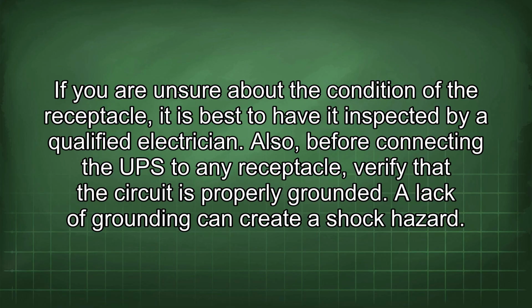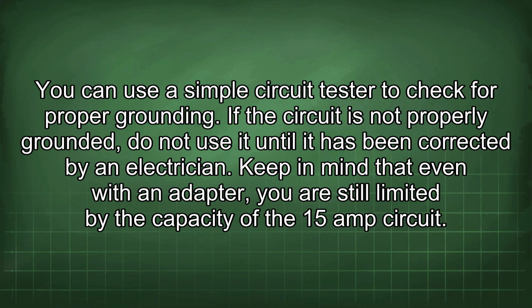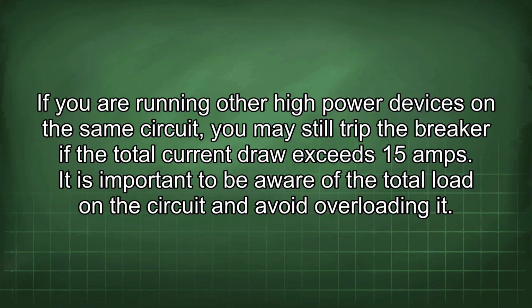electrician. Also, before connecting the UPS to any receptacle, verify that the circuit is properly grounded. A lack of grounding can create a shock hazard. You can use a simple circuit tester to check for proper grounding. If the circuit is not properly grounded, do not use it until it has been corrected by an electrician. Keep in mind that even with an adapter, you are still limited by the capacity of the 15 amp circuit. If you are running other high-power devices on the same circuit, you may still trip the breaker if the total current draw exceeds 15 amps. It is important to be aware of the total load in the circuit and avoid overloading it.